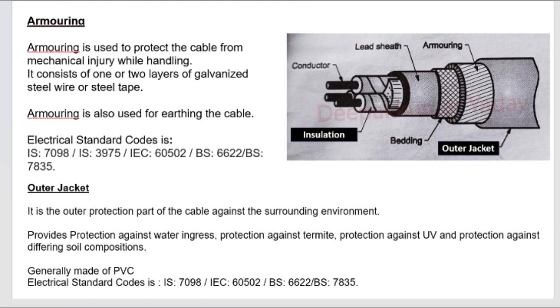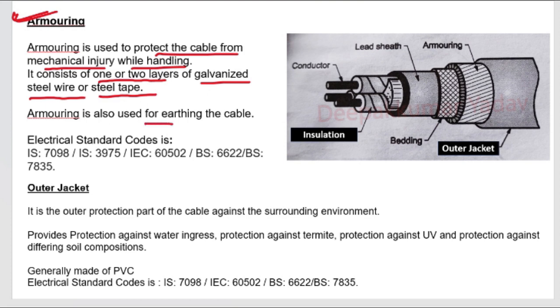After the bedding, the next protective layer is armoring. Armoring is used to protect the cable from mechanical injuries while handling. It consists of one or two layers of galvanized steel wire or steel tape. Armoring is also used for earthing the cable. Electrical standard codes are IS 7098, IS 3975, IEC 60502, BS 6622, and BS 7835.